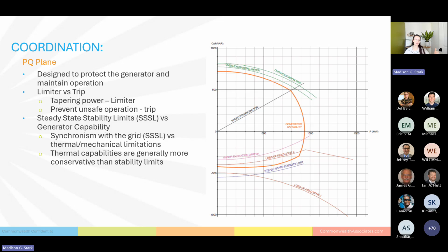Now, when we move into the under excitation portion, the first thing we're going to hit is the under excitation limiter. Good. And you might ask, why is that one inside the generator's capabilities? We'll get to that in a second. The next thing we're going to hit is this loss of field zone 2 relay. This is a slow acting time-based relay. It's going to give the generator a second to correct itself and get back to this limit, and then it's going to trip to protect the generator. We then hit this under excitation capability curve for the generator. And then we hit our loss of field zone 1 relay. This is a fast acting relay. It's going to trip instantaneously.